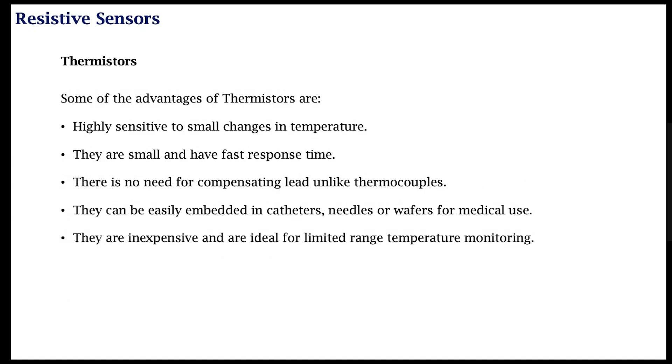That is not needed in a thermistor. And because they are really small, they can be embedded inside catheters and they are relatively inexpensive and quite useful for measuring temperature within a small range, which is what we do usually, for example in fever temperature measurement systems. We measure temperature within a relatively small range because it is highly unlikely for the human body temperature to go below, for example, 30 degrees Celsius and to go above 40 to 45 degrees Celsius.